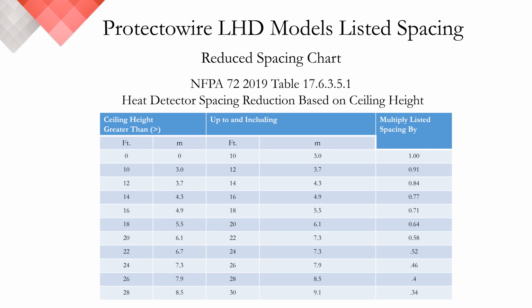To illustrate this, consider our 50-foot spacing per UL on our 155 detectors. The 50-foot spacing is allowable only on ceilings up to and including 10 feet. As the ceiling height increases, the derating multiplier decreases. So, to apply some simple math, at 30 feet, what was once our 50-foot spacing now becomes a factor of 0.34 times that listed spacing. So, 50 feet times 0.34 gives us a net figure of 17 feet for our new listed spacing figures.